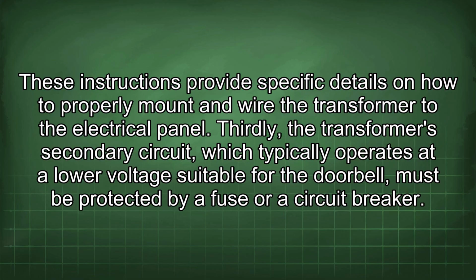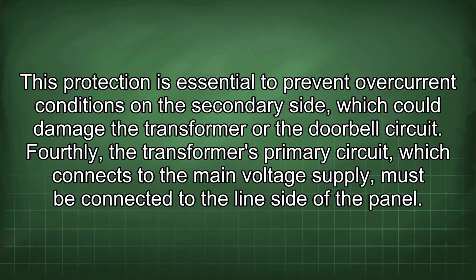Thirdly, the transformer's secondary circuit, which typically operates at a low voltage suitable for the doorbell, must be protected by a fuse or a circuit breaker.